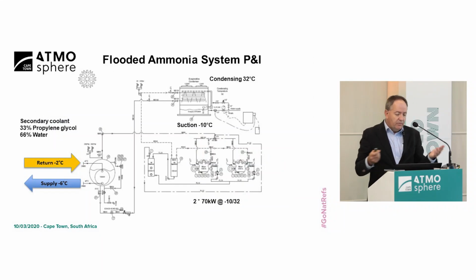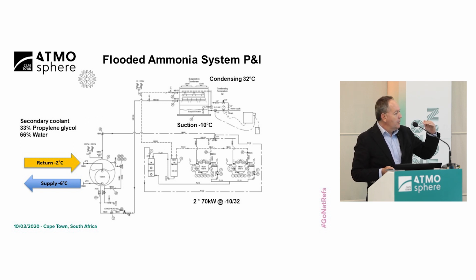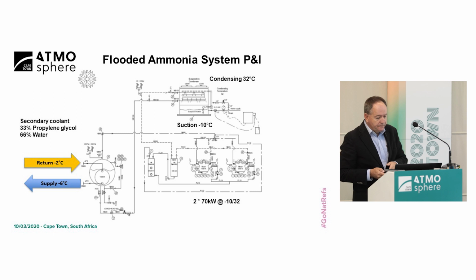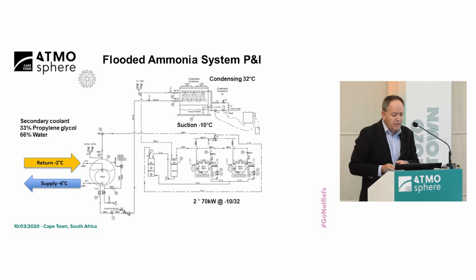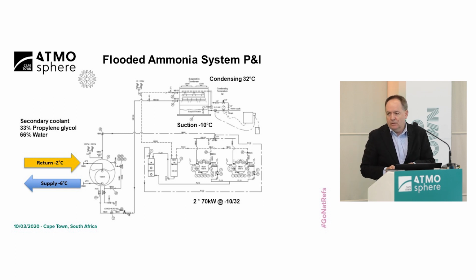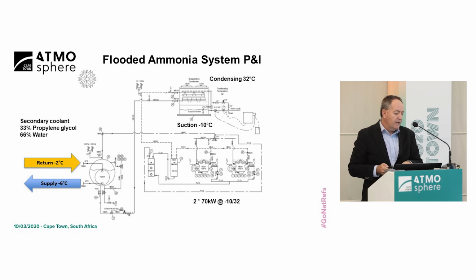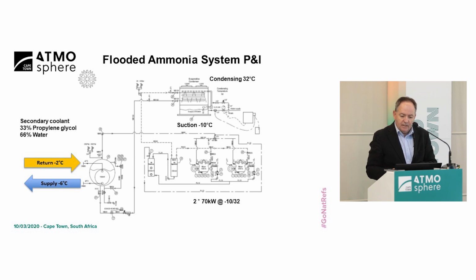level. I don't know if you can see that too clearly, but there is an evaporative condenser, as is normally the case with an ammonia system. We designed for an operating condition of -10, so we actually edged that up a bit. We didn't really need -10 to maintain a room temperature of 0. For condensing, our target was 32 degrees. A mistake we made in Stellenbosch: a wet bulb of 22 was a little bit too marginal on a really hot day. Fortunately we had variable speed drives on the evaporative condenser, so we could get more air through there and lower the condensing. So that saved my bacon on that side.